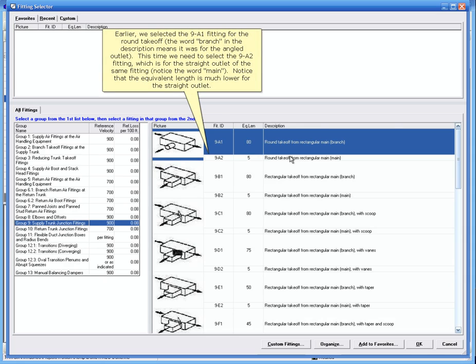Earlier we selected the 9-A1 fitting for the round takeoff. The word branch in the description means that it was for the angled outlet. This time we need to select the 9-A2 fitting, which is for the straight outlet of the same fitting. Notice the word main. Notice that the equivalent length is much lower for the straight outlet.